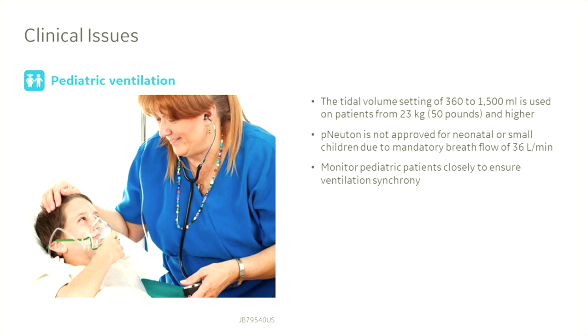Let's address some additional clinical environments where the ventilator may be used. Pediatrics. For pediatric usage, remember that the pNeuton ventilator is approved for patients 23 kilograms and above. The pNeuton can be used as a pressure-limited ventilator measuring volumes and inspiratory time. Clinicians should monitor respiratory rate pattern as the ventilator's fixed flow rate at 36 liters per minute may be too high for some pediatric patients.